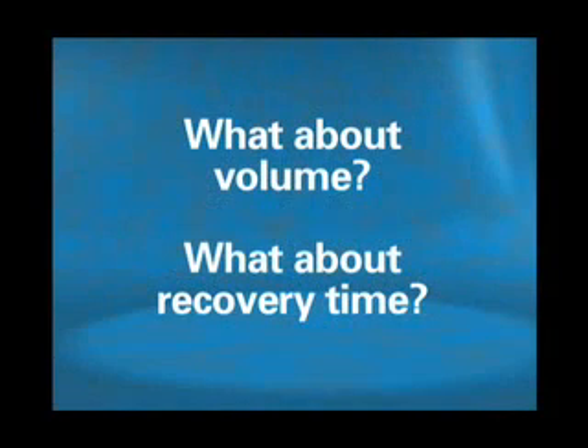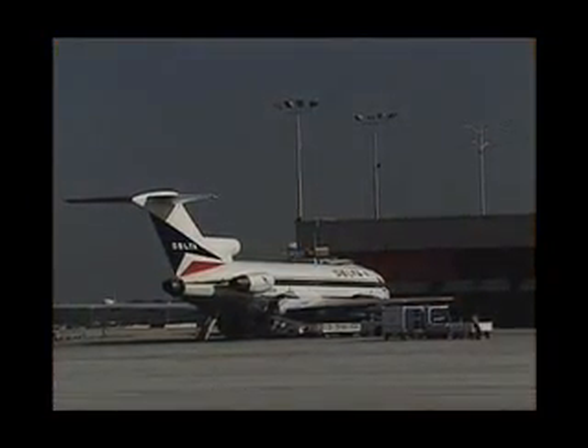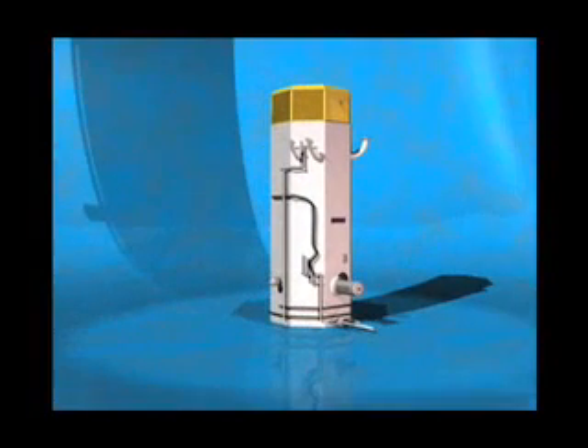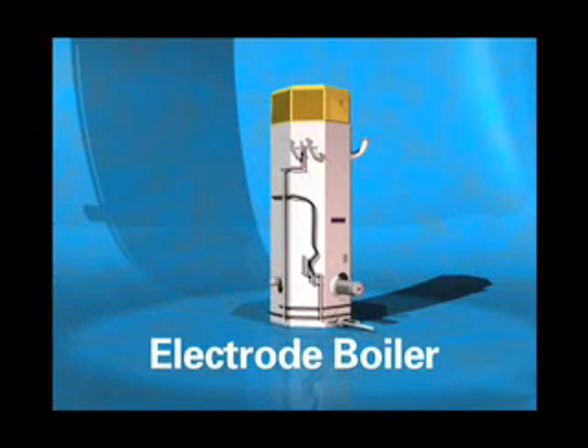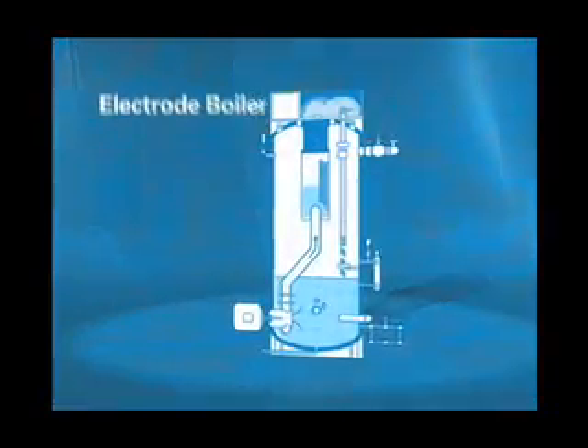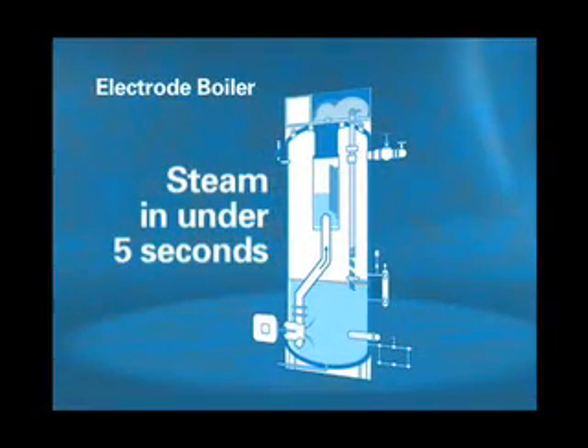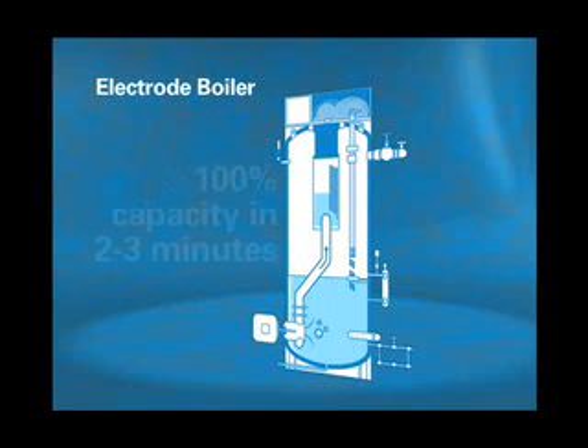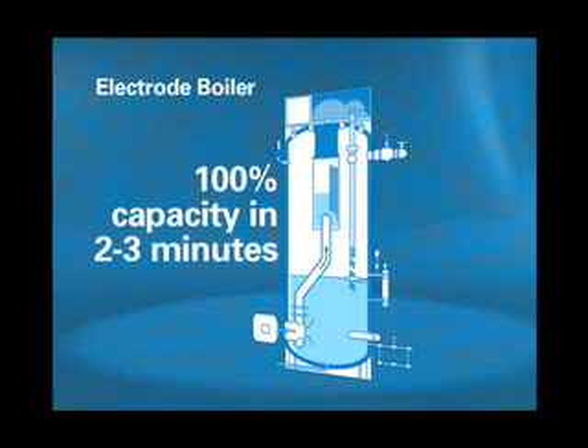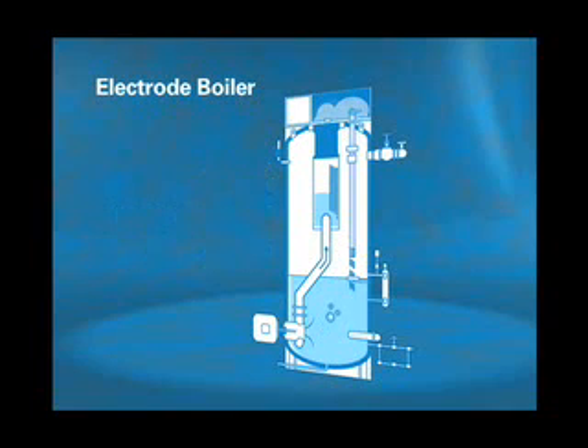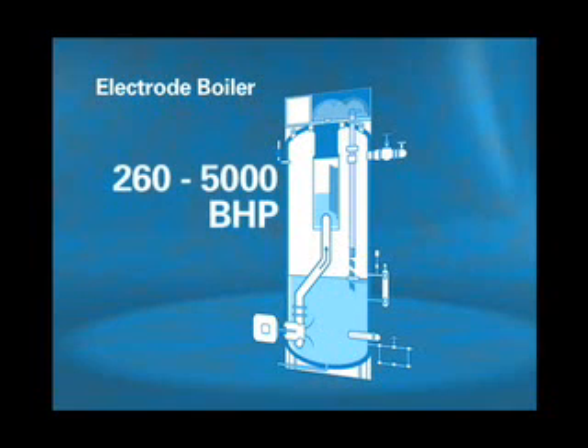Let's talk volume and recovery time. What if I need a whole lot of hot water or steam really fast? How about enough heat to heat a commercial airline hangar? There's a type of electric boiler that can do that. It's called an electrode boiler. Instead of resistance heat, an electrode boiler uses the water itself to conduct high voltage. It can turn water to steam in just a few seconds. How's that for fast? Steam in seconds. Yep, that fast. You can be at 100% capacity in just 2 to 3 minutes instead of 2 to 3 hours. Electrode boilers are available in sizes ranging from 260 boiler horsepower all the way up to 5,000.